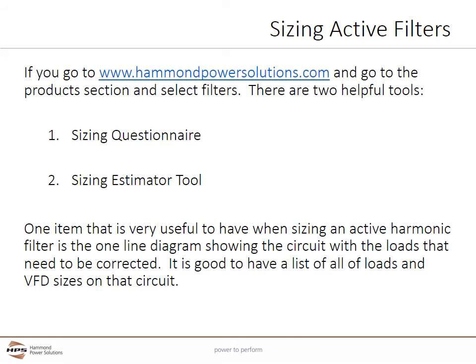Active filters can be sized on Hammond Power Solutions' website at www.hammondpowersolutions.com. Once there, go to the product section and select filters. There are two helpful tools: a sizing questionnaire and a sizing estimator tool. Using the sizing questionnaire, collect the information needed for the size estimator spreadsheet. Once the questionnaire is completed, the information can be entered into the sizing estimator, or it can be sent to Hammond Power Solutions where one of our power quality experts can review and provide a properly sized active harmonic filter solution. One very useful item when sizing an active harmonic filter is a one-line diagram showing the circuit with the loads that need to be corrected, along with a list of all loads and VFD sizes on that circuit.